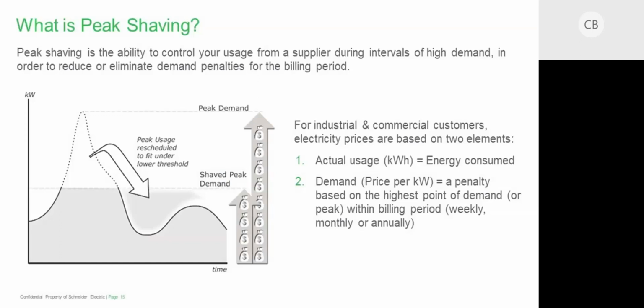But what I will say, in the data center world, what I expect to see is a change in the load profile to become more dramatic and more peaky. And what's driving that? It's the IT kit. The IT kit of yesterday was sitting there in the rack online with 0% CPU utilization. You may be consuming 55% of nameplate rated kW capacity. And as you start using that CPU utilization, it may go up to 65%, 70%. We rarely ever see 100% kW demand on that equipment. But the new servers today at idle, they are operating at 10% or less of the nameplate rating.